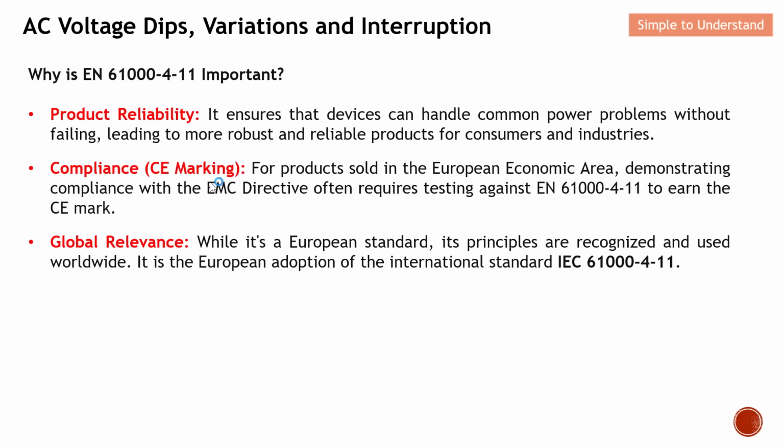If you don't do this test, you cannot sell your product in Europe. In short, this is for products sold in the European Economic Area. Therefore, you need to demonstrate compliance with the EMC directive. Often you are required to test against this standard so as to earn your CE mark. Basically, this is mandatory, because you actually need to comply with this standard.